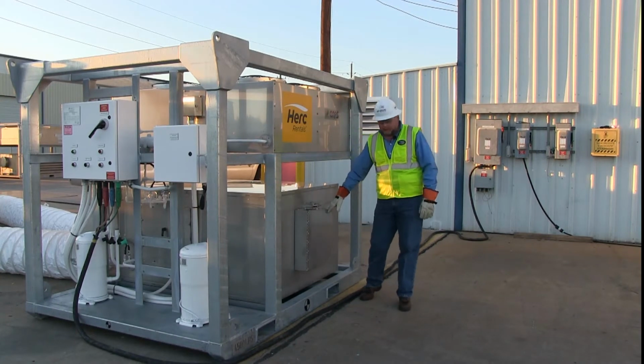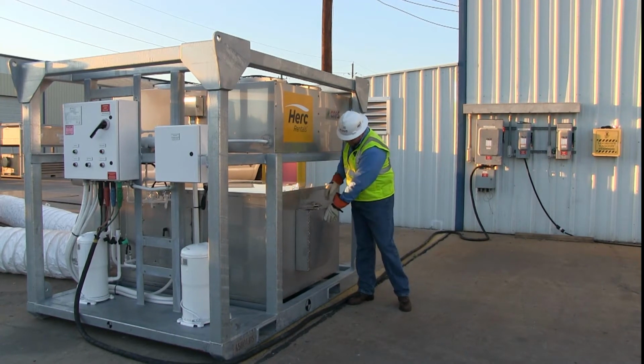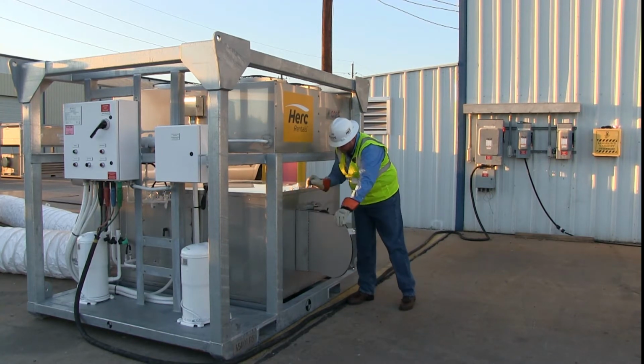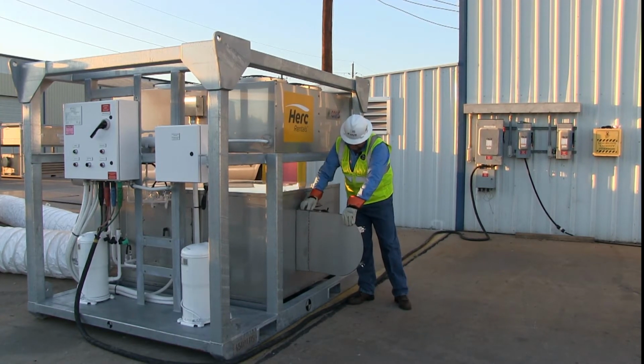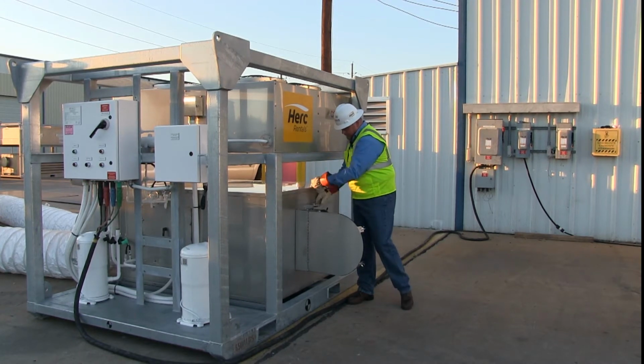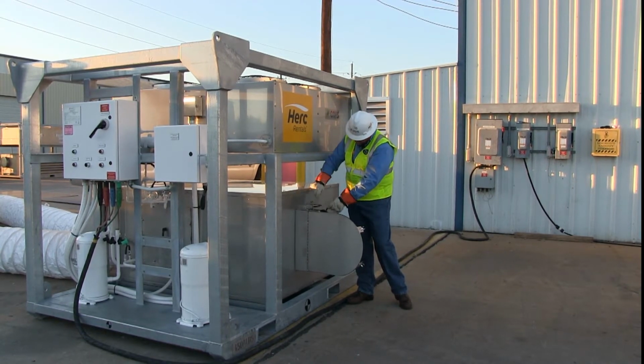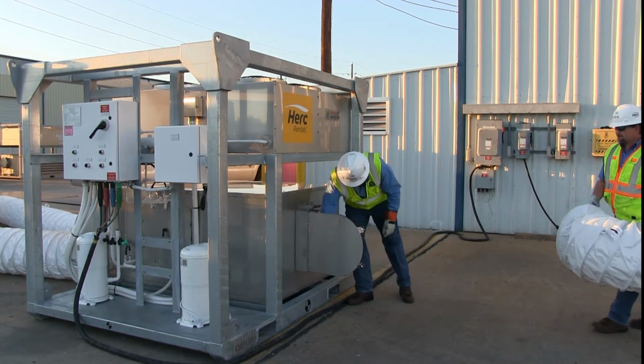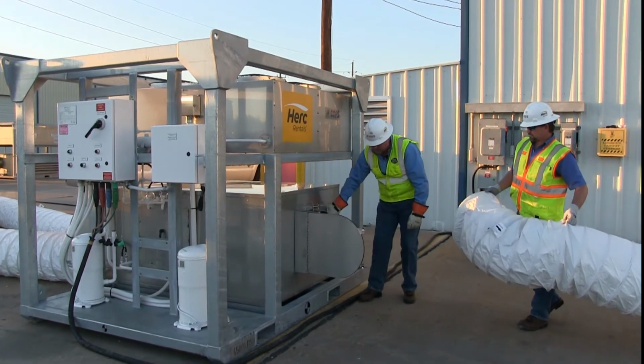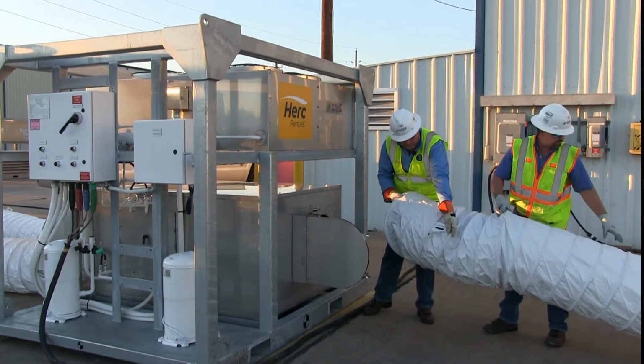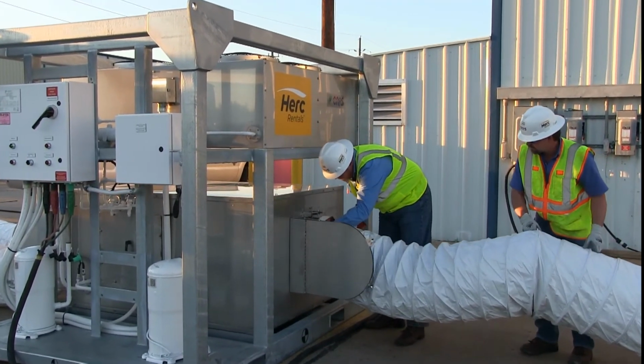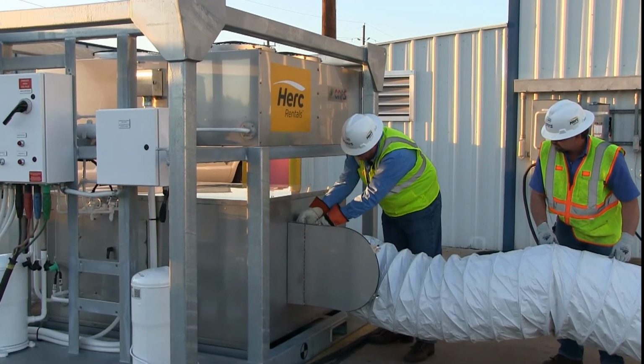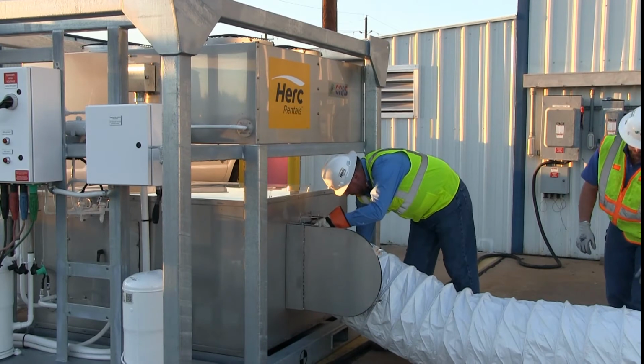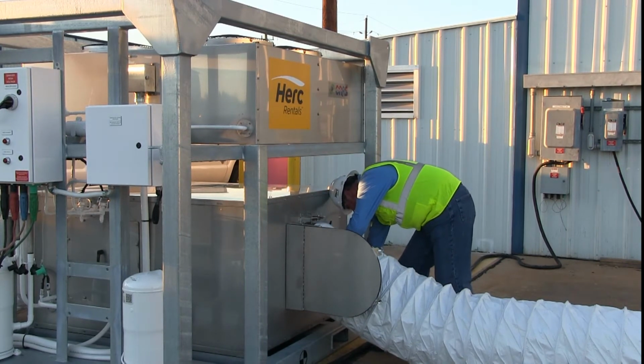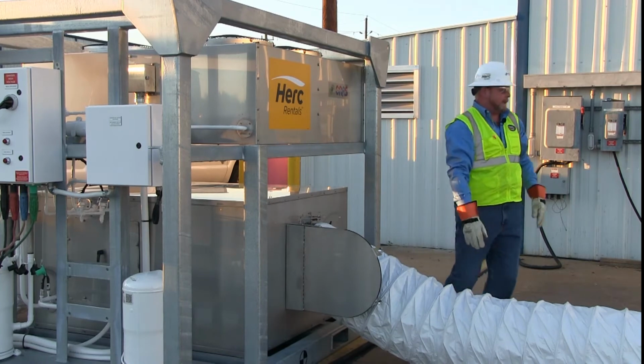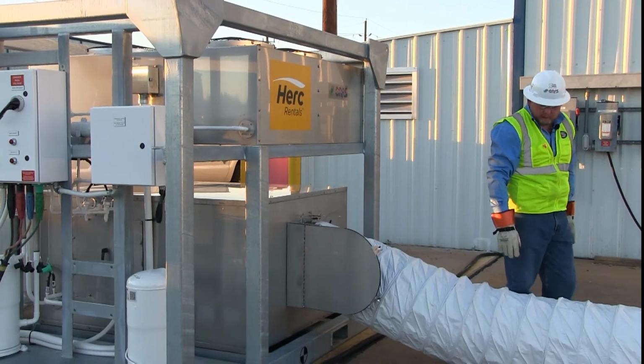Now that we've got the return ducts hooked up, we're now going to hook up the supply duct. It works the same way. We pull the pin, pull the Jeep latches off, put the pin back. Now the supply duct does have an adjustable damper on it. You're going to set it in a full open position. Open up the 4 friction clamps, all 4 sides. Direction of airflow is going out of the machine there. I'm going to hook up the ducts to it. Drop the 4 friction clamps on top of it. There we go. It's locked up, and then that will plumb into the building or into the area being served.